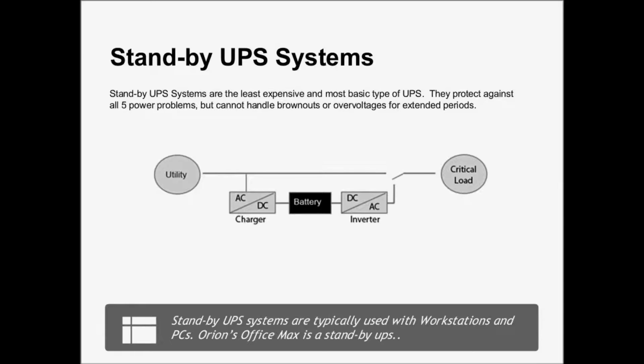Basically what it does is, you get power coming in from the utility, and it watches the power come through, and if it goes outside of that range, it throws a high-speed switch and runs off a battery and then powers your load. And if it goes back in the range, it switches back to utility power. So it's a very basic design, but for workstations and less critical loads, that's a great way to go.